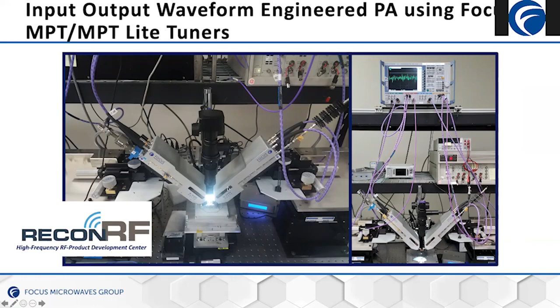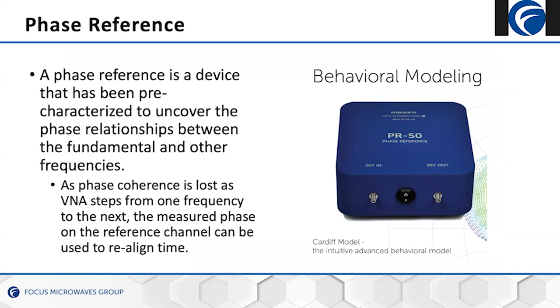And again, it all ties together with what we call the phase reference. This is a pre-calibration that we do at the factory, and it correlates the phase variation between the fundamental and the harmonic frequencies. We do this calibration ahead of time, and then we ship it to the customer, and then there are just a few calibration steps to make this right. So when we actually measure the A and B waves, all of it is correlated and makes sense.